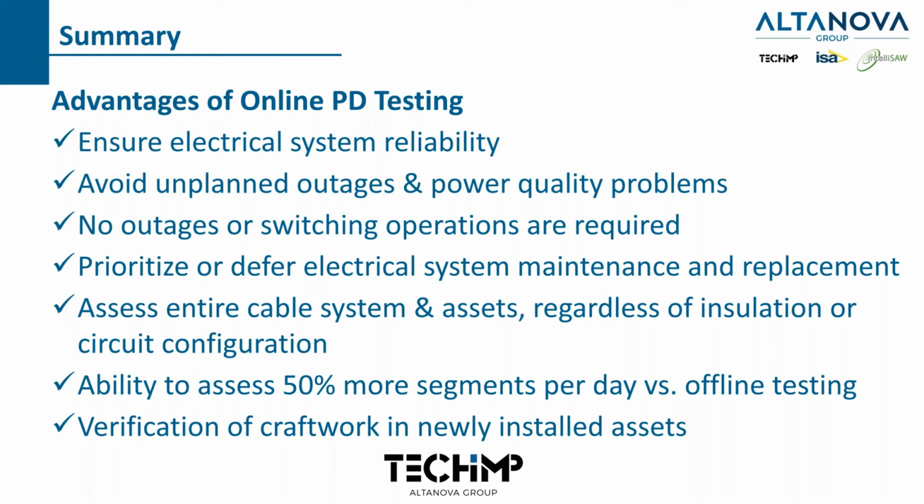And we also can verify craft work. So if you put in a new asset, say a cable termination, or put in a new transformer, and you want to verify the craft work's done, we can verify that as well. Another advantage to online testing.